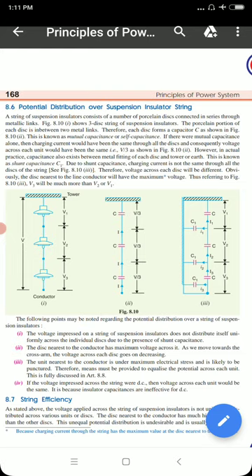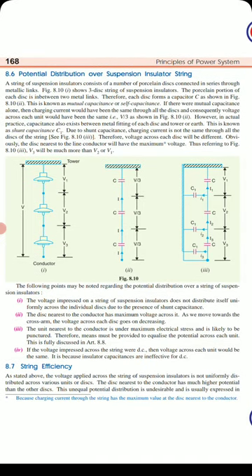Because of the shunt capacitance, in actual practice V1, V2, V3 will not have the same values. The insulator nearest to the conductor has a higher voltage than the insulators closer to the tower. Specifically, V3 — the lowest insulator nearest the conductor — has the most voltage, and the voltage decreases progressively as we move toward the tower.